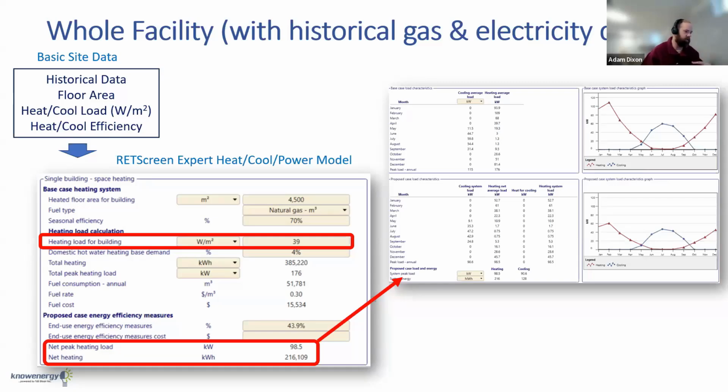That then further reduces that fuel consumption to reconcile back with. Then I'm able to tweak up this number, heating and cooling load for the building, to get that 51,780. So once I've done that, that's the building as is. But let's say I wanted to do some energy efficiency measures in your building. So you could also do that. We always recommend reduce your waste, maximize efficiency, then optimize supply. So doing those first 2 steps before you actually go out there and buy a new heat pump or a new heating and cooling system.